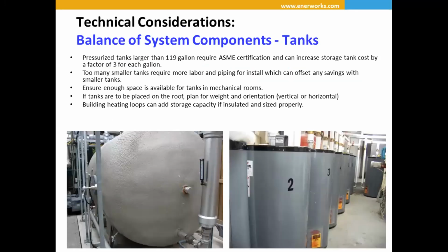Storage tank, so this is really important. This is your battery. So if you're generating electricity and you want to store it, you use batteries. Our battery is essentially hot water, a nice inexpensive solution. And essentially you're going to match the storage tank to the load that you're trying to save for the day. So for instance, if you have a 900-gallon load and you want to save roughly 35%, you're going to want to be able to store at least 300 gallons of fluid and size your system accordingly.